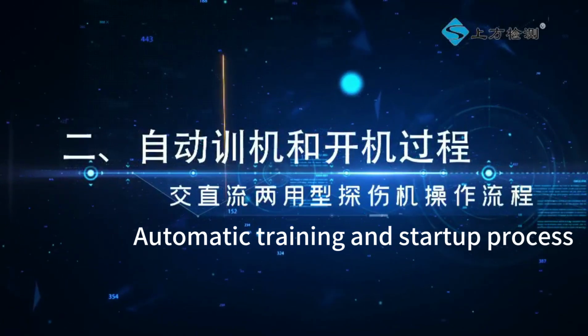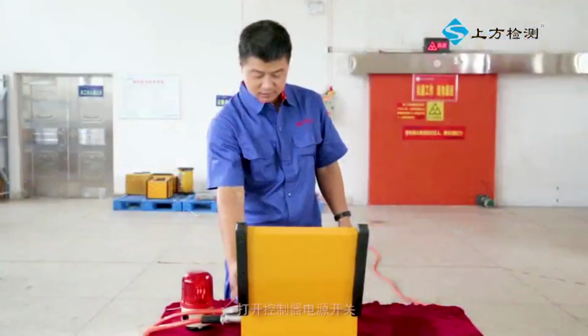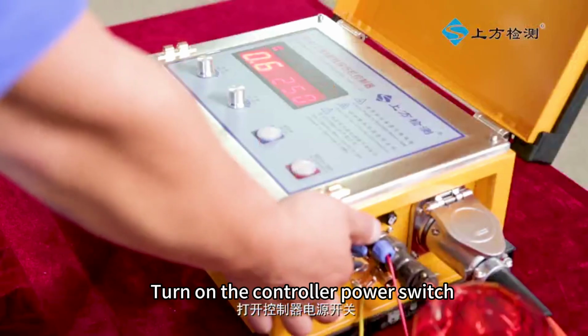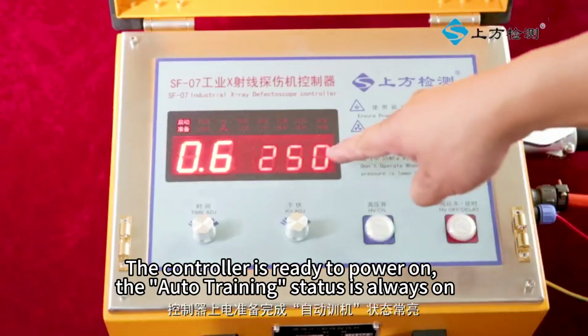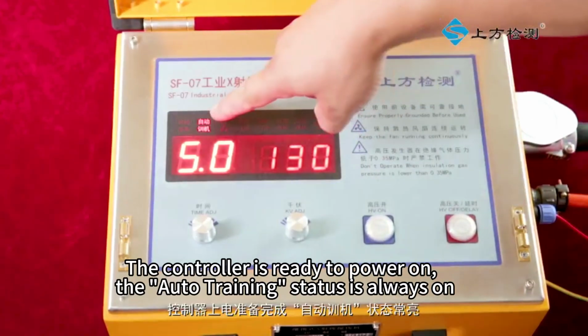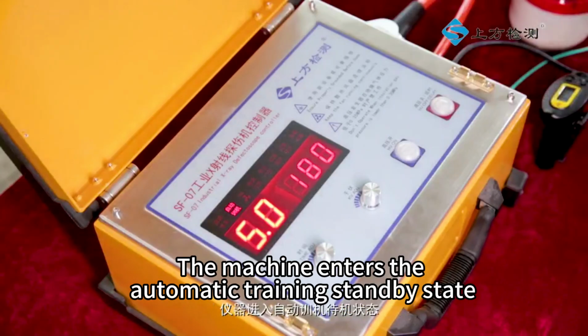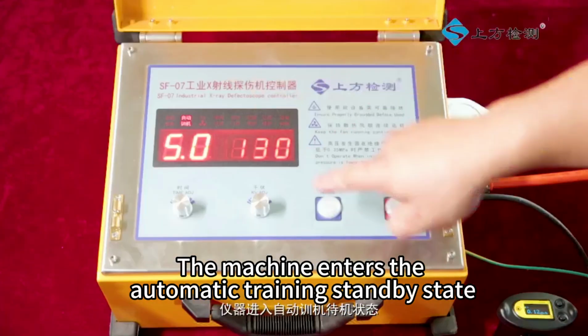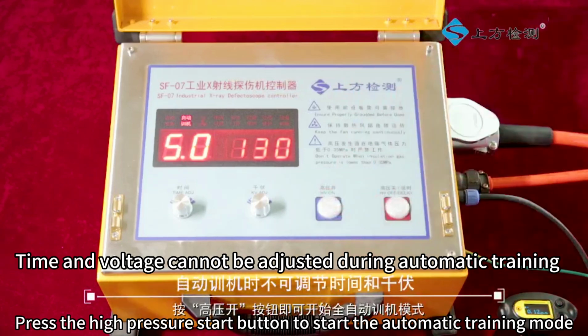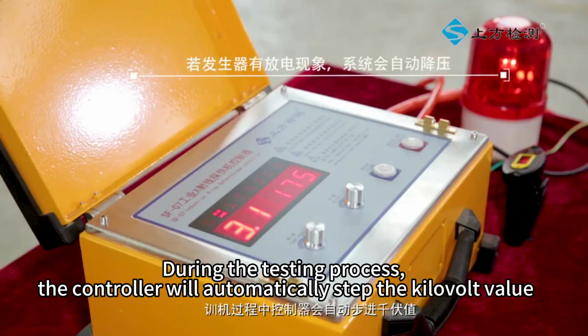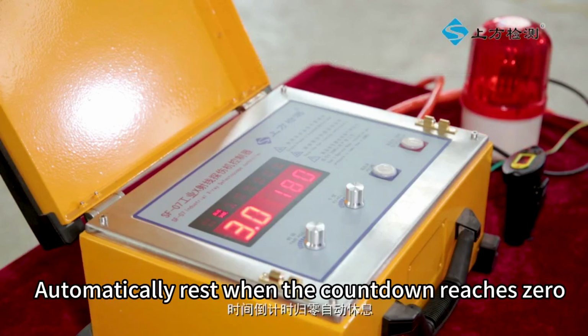2. Automatic training and startup process. Turn on the controller power switch, the controller is ready to power on, and the auto training status is always on. The machine enters the automatic training standby state. Press the high pressure start button to start the automatic training mode. During the testing process, the controller will automatically step the kilovolt value. It automatically rests when the countdown reaches 0.